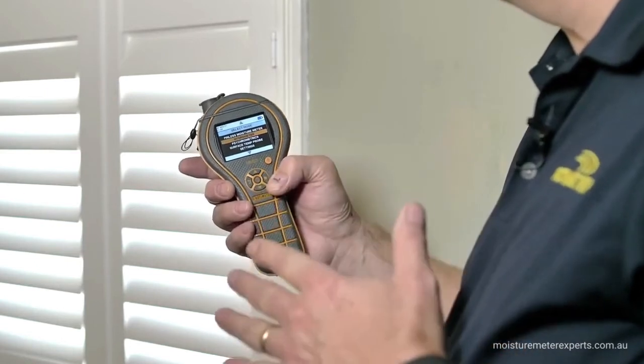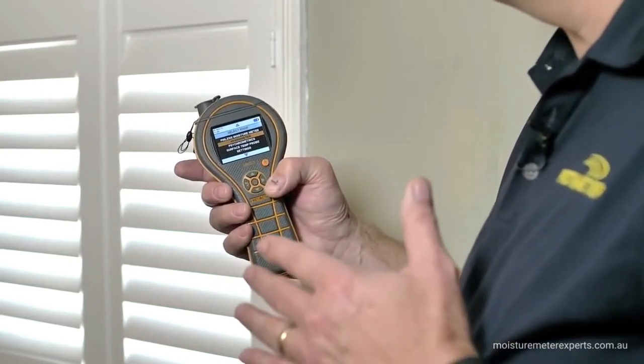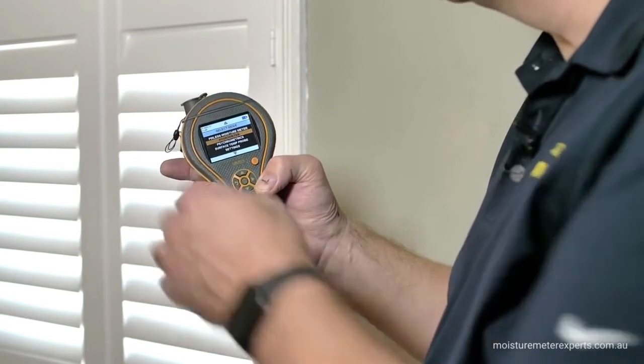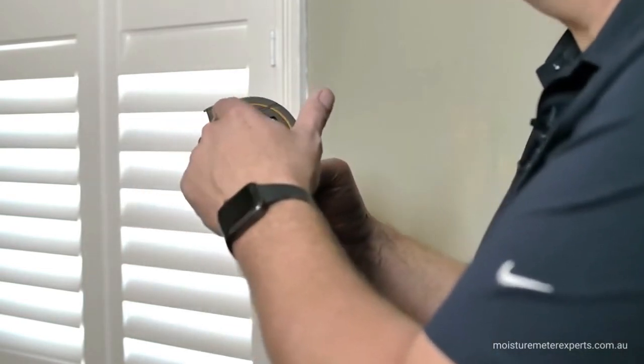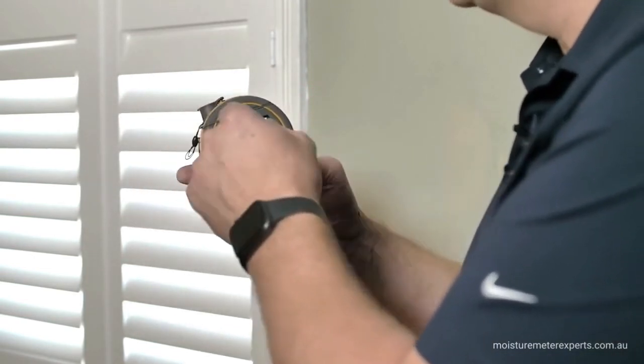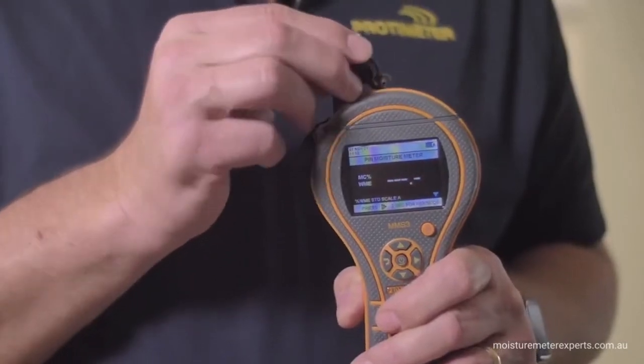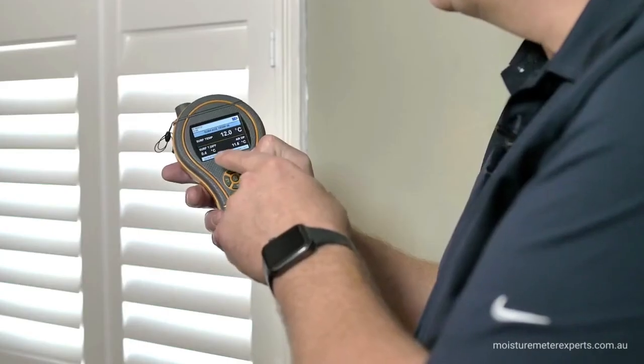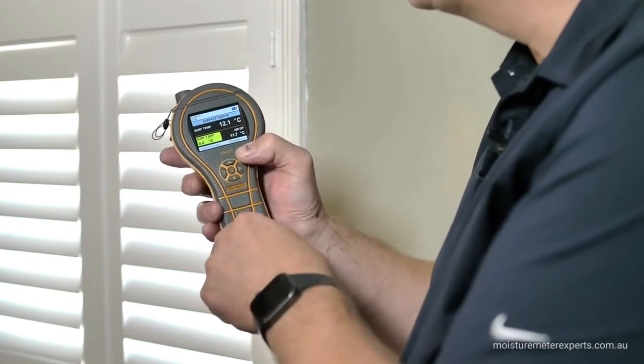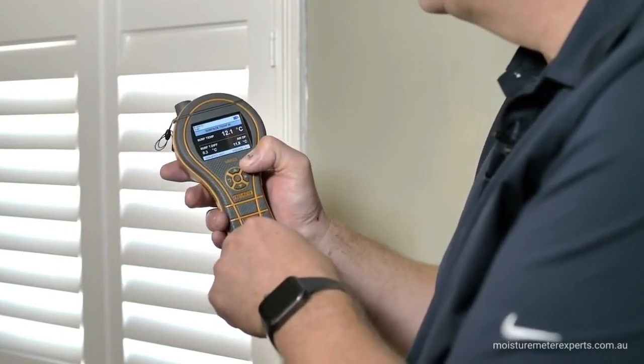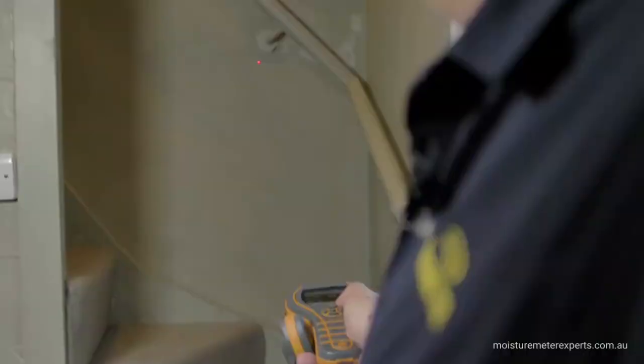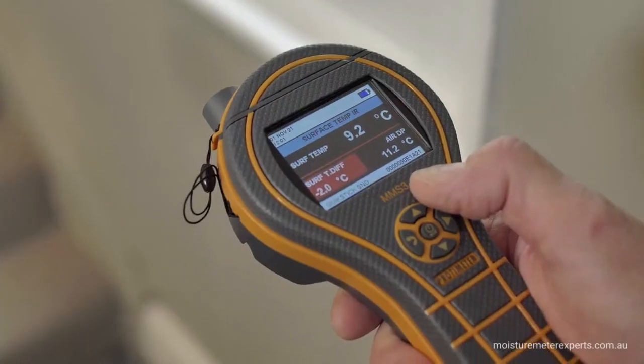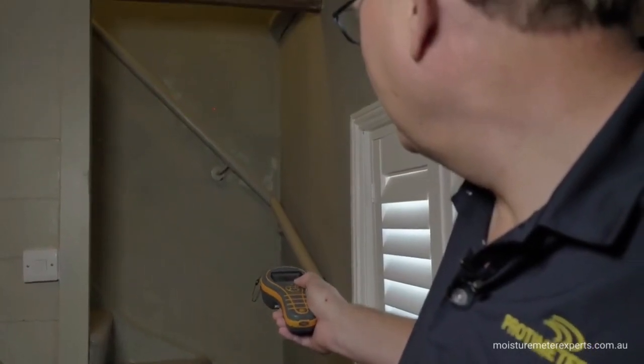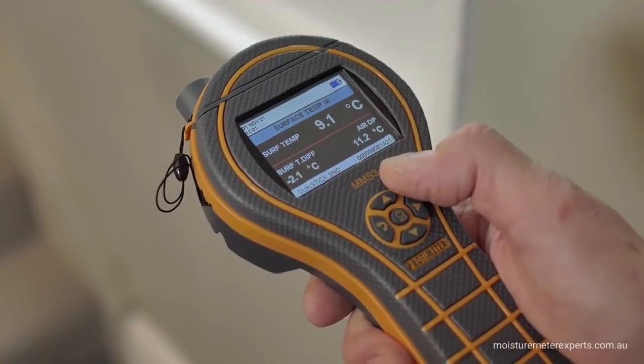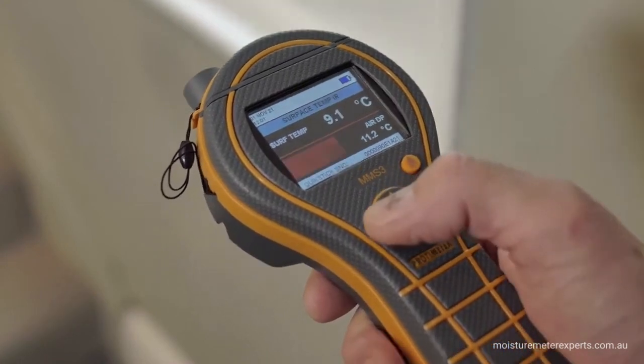Now we're going to use the moisture meter to determine whether we have condensation in this building. In order to do that, we're going to use the non-contact surface infrared thermometer here. You can remove the rubber cap here. We press it once for the reading and then twice to engage the laser pointer. And now we're directed at the wall. And you can hear the audible change immediately, showing that it is indeed condensation, and we are at 2.1 degrees below dew point on this particular surface.